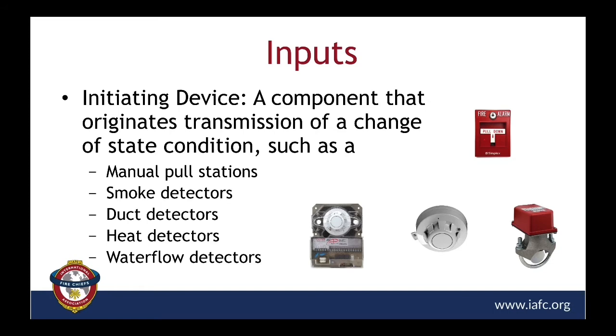Now, after operation, the fire alarm pull station must be restored to the normal non-alarm position by using a special tool or key, and that is needed to reset the control unit. So initiating devices that are automatically activated, needless to say, require no human intervention, and they respond to a number of detectable physical changes that are byproducts of a fire.